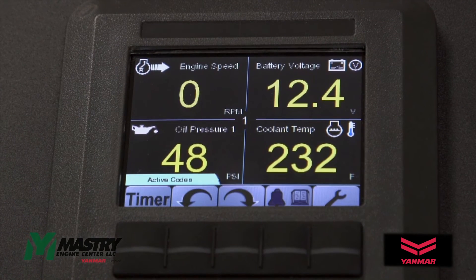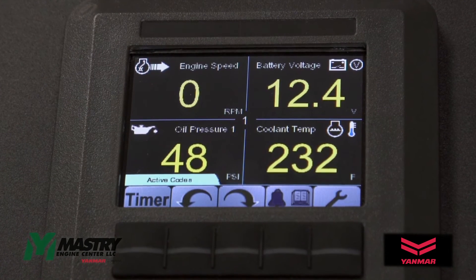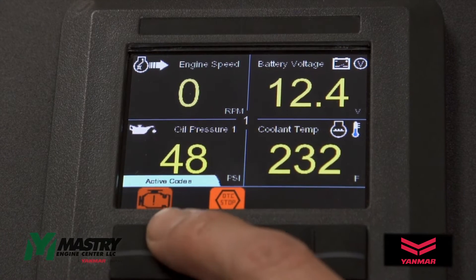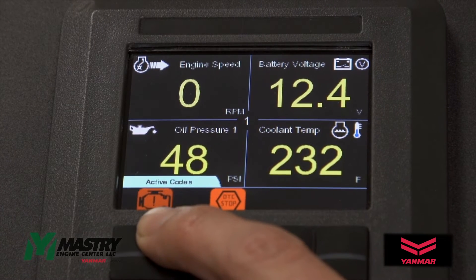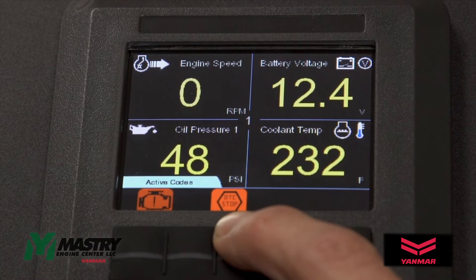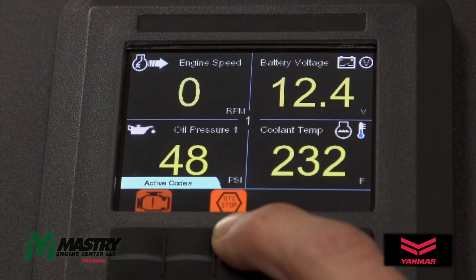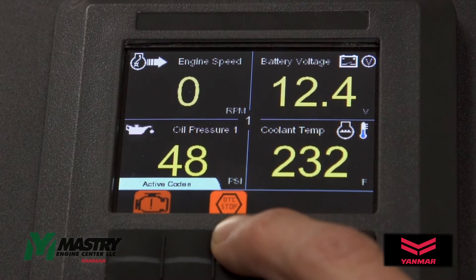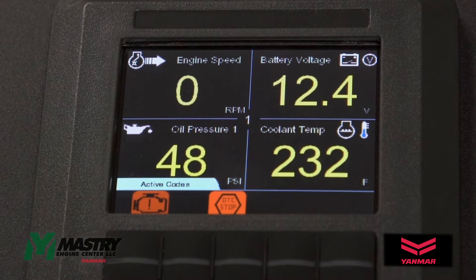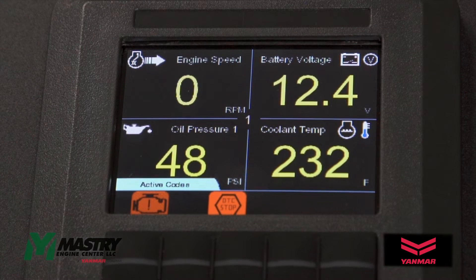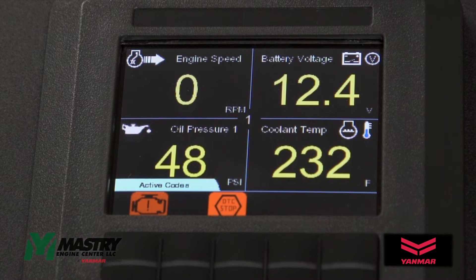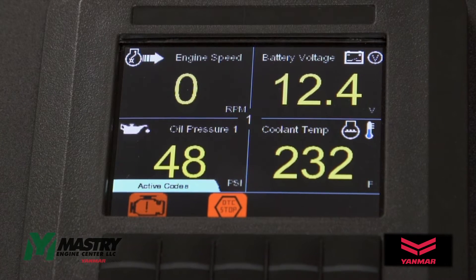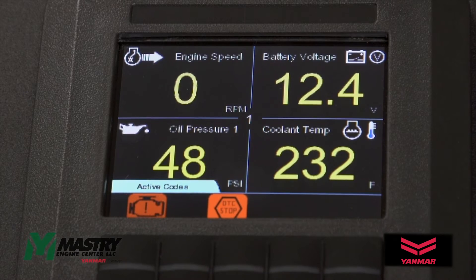You can acknowledge this fault code and then you'll see the engine speed has dropped to zero. We now have an active fault code icon, but we also have a DTC stop icon indicating that this particular fault code has shut down the engine. The two fault codes that can shut down the engine are coolant temperature fault codes and a low oil pressure fault code.